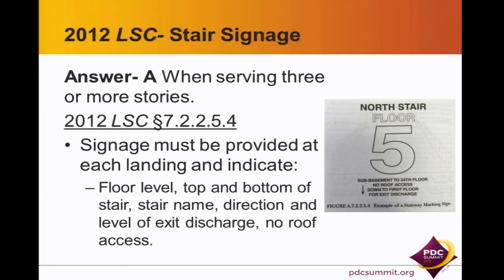And I'm going to offer a personal interpretation on this. The code says that the sign is to be visible with the door open or closed. And I actually had a facility cited during the survey process because the person was in the corridor outside the stair and the stair door was closed and they couldn't see the sign. And I said, no, the intent is for someone inside the stair. So if you happen to run into that surveyor, you might challenge that finding.